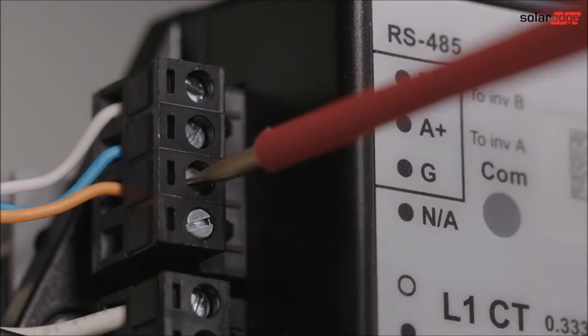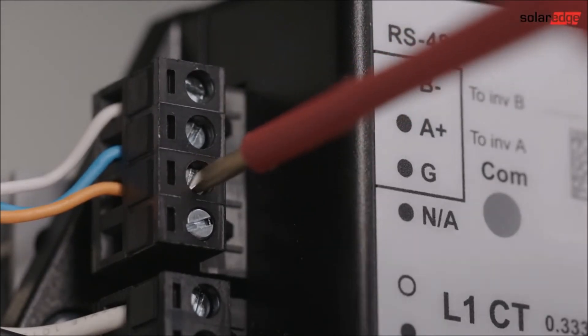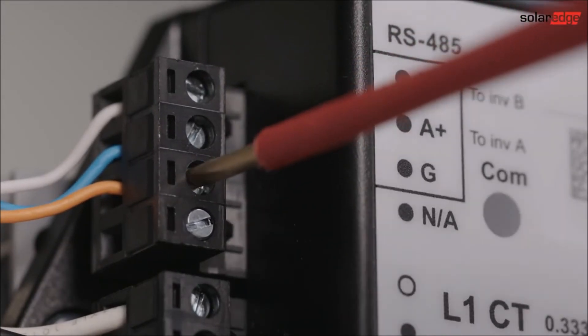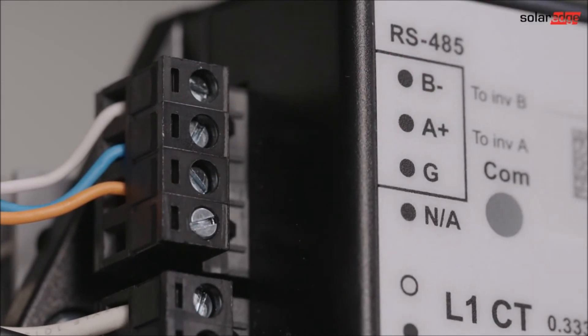Next up is the connection of the RS485 bus. We recommend using a CAT5 cable. A twisted pair must be used for terminals B and A between meter and inverter. We recommend using the white and blue wires. For the G terminal any other wire can be used. We recommend using orange.